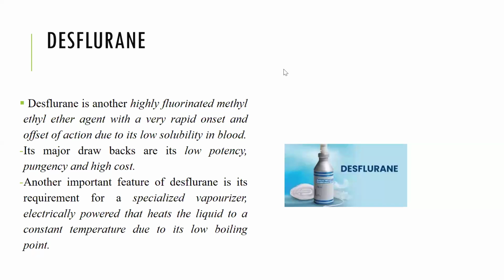So desflurane is another highly fluorinated methyl ethyl agent with a very rapid onset. In fact, it's described as ultra short-acting due to its low solubility in blood. However, its major drawback is low potency, pungency, and very, very expensive. Another important feature of desflurane is its requirement for a specialized vaporizer, which is electrically powered, heating the liquid to a constant temperature because of its low boiling point.